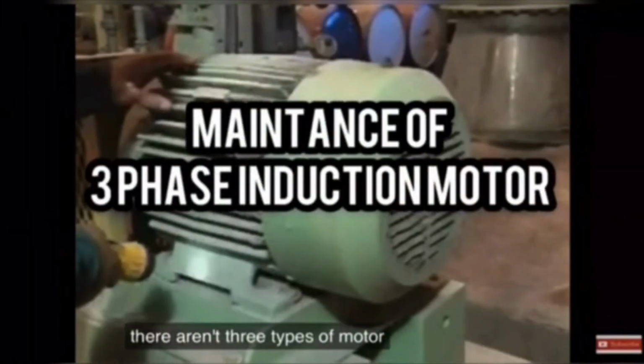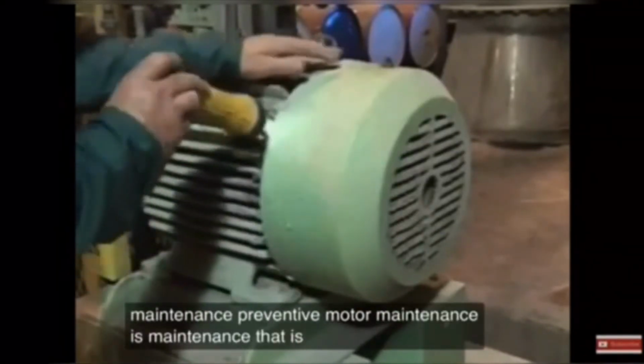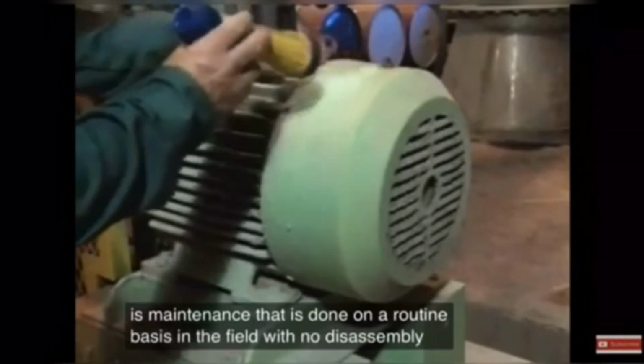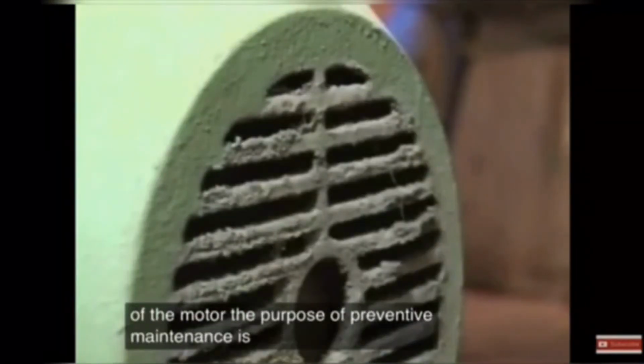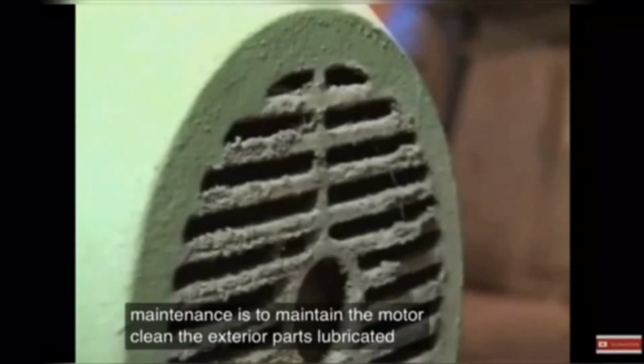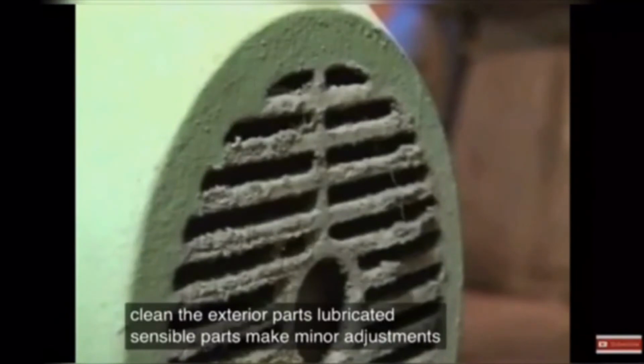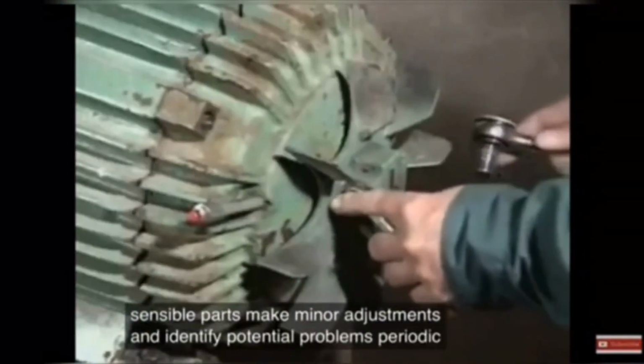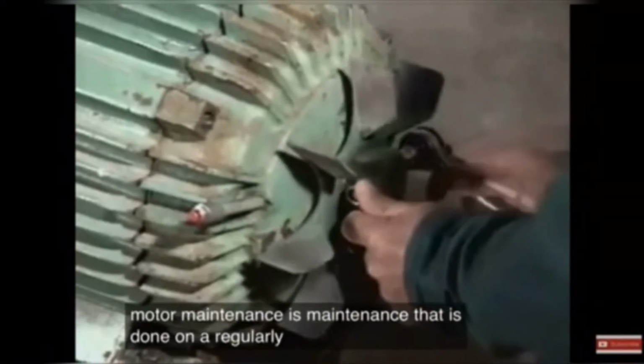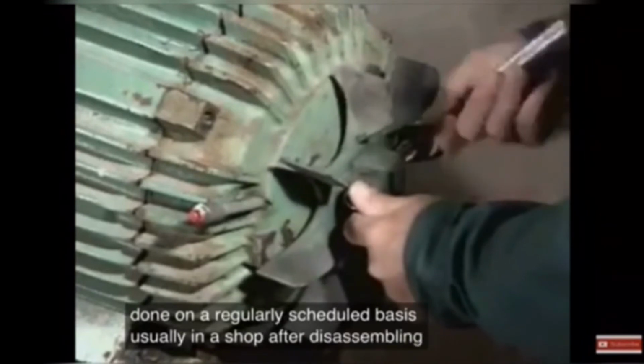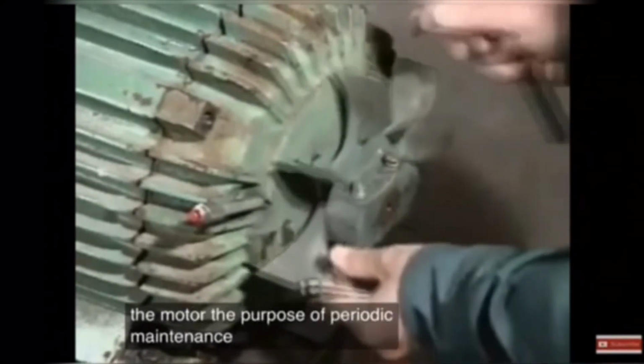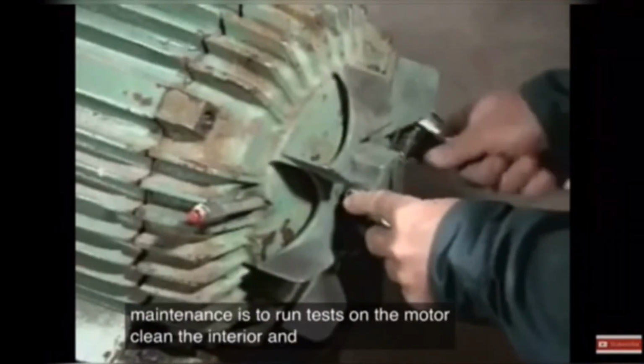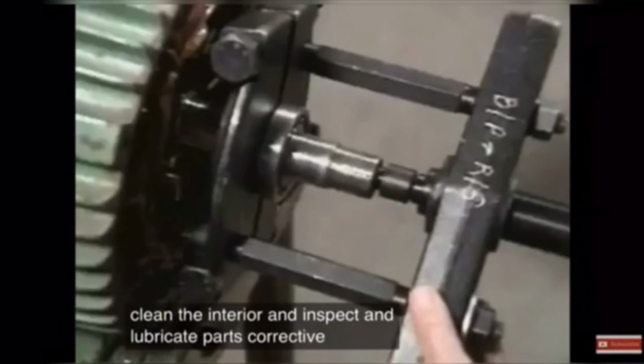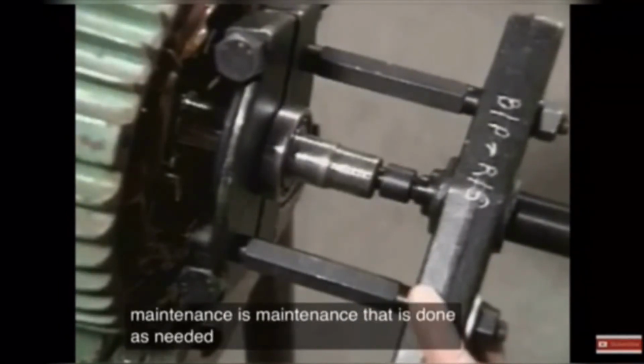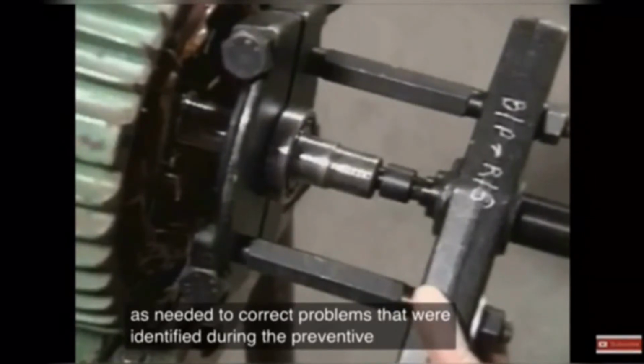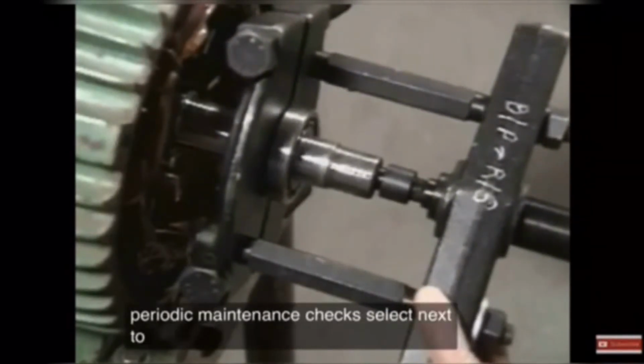There are 3 types of motor maintenance. Preventive motor maintenance is maintenance that is done on a routine basis in the field with no disassembly of the motor. The purpose of preventive maintenance is to maintain the motor, clean the exterior parts, lubricate accessible parts, make minor adjustments, and identify potential problems. Periodic motor maintenance is maintenance that is done on a regularly scheduled basis, usually in a shop after disassembling the motor. The purpose of periodic maintenance is to run tests on the motor, clean the interior, and inspect and lubricate parts. Corrective motor maintenance is maintenance that is done as needed to correct problems that were identified during the preventive and periodic maintenance checks. Select Next to continue.